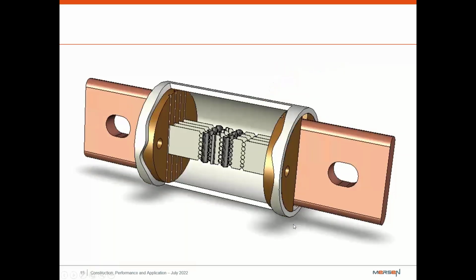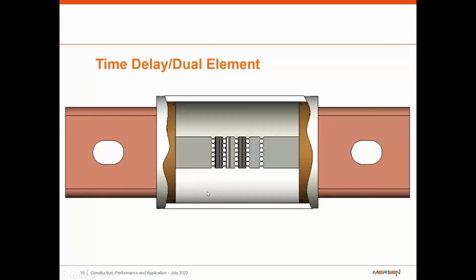Inside the body is where we're going to have a filler, and this is going to be the sand that we actually make ourselves, taking out all the impurities. It's not going to be like beach sand or anything like that. And the reason for that is, whenever the arc comes in contact with the sand that's inside, it'll turn into a glass or an insulating material, and it'll open the circuit. So in the case of a short circuit, which we'll get into in a little bit, it'll cover the entire element. With the time delay, it's going to be a little bit different.